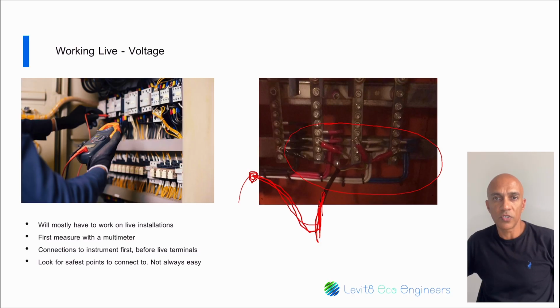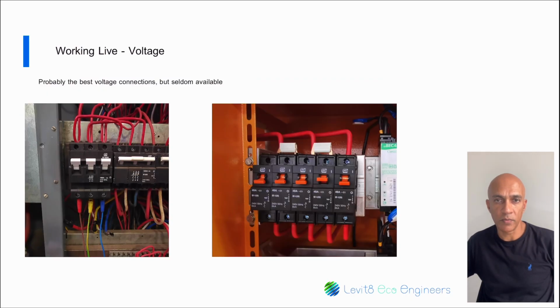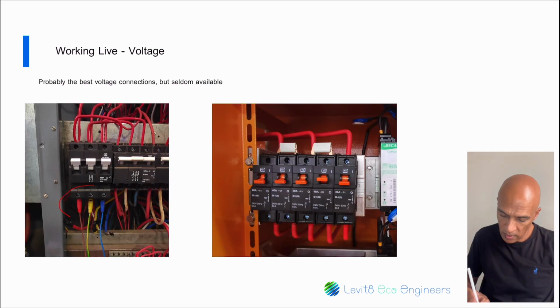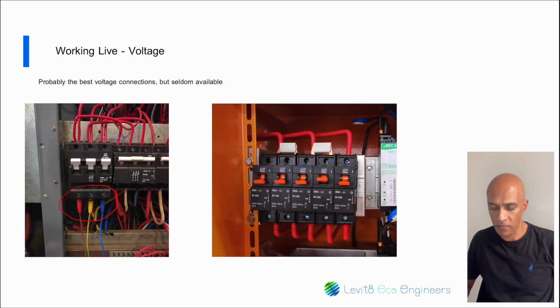So these photos now show points at which I have measured typically. Okay, so we've previously discussed this photo on the left. And if you have a look at this photo, these connections are very secure because they've been screwed into the terminals of the circuit breaker. So the weight of this cable is not going to really be an impact on those leads. You obviously want to make sure that your banana connections are in good condition.